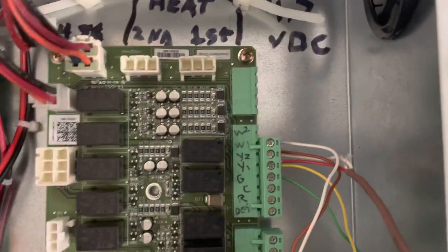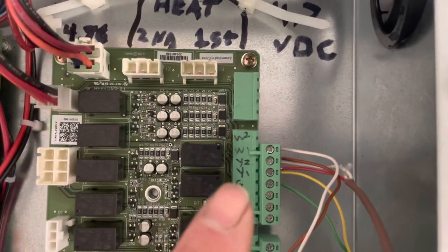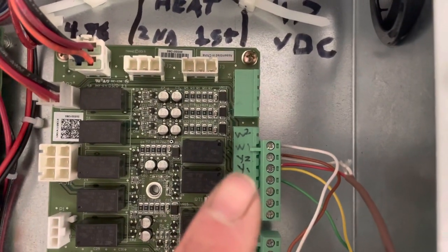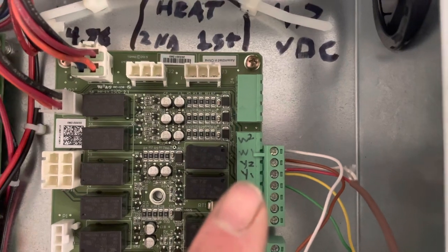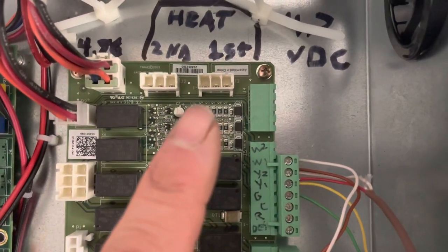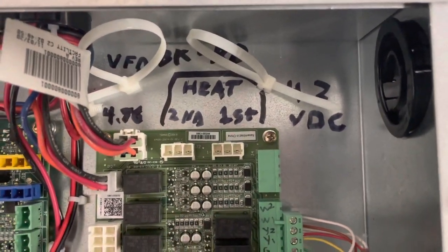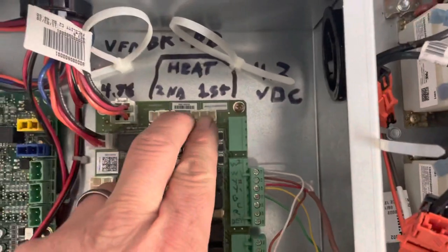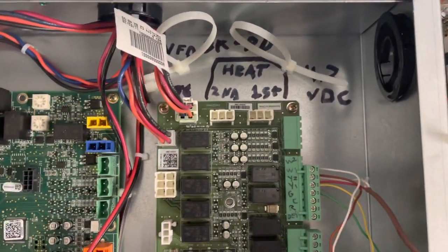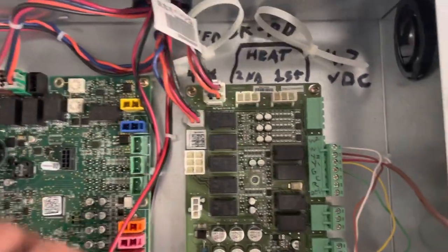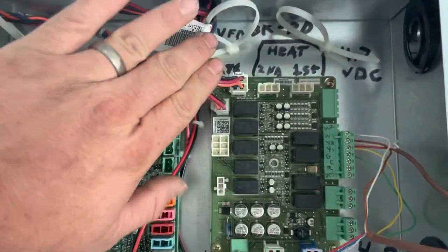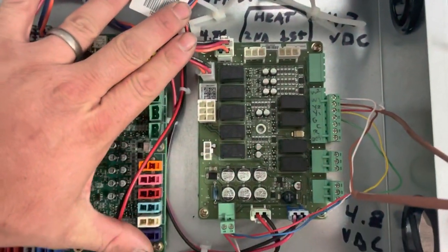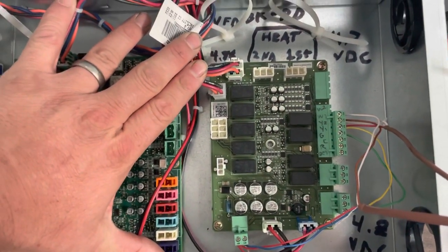So I don't have my W2 hooked up, but W1 goes in there, of course, for my heat. And you would hook your heater up to here, heat stage one. So you get 24 volts out of there if you put on your electric heat. But that's it. Like I said, you won't need your options module or anything with any of this.